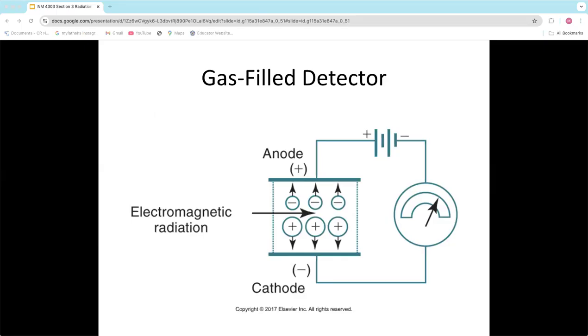Okay, so with gas-filled detectors, I mentioned a minute ago, we're going to talk about GM meters, we're going to talk about ionization meters, and we're going to talk about a dose calibrator. So that will apply to all of those. And this would apply to a surgical probe, like I said, we won't mention. But I'm going to cover kind of the basic principles of how they work, and then we'll get a little bit more specific on what the difference between it being a GM meter or being an ionization chamber, and then get specific on the dose calibrator, okay?